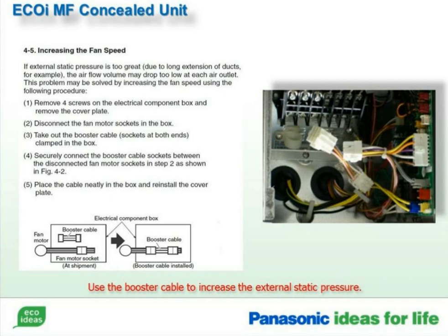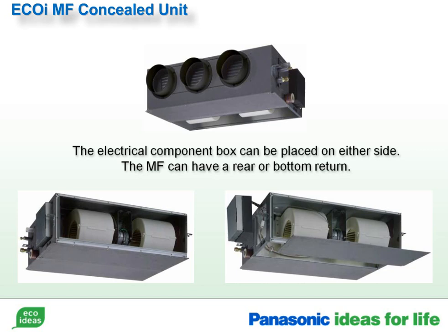To achieve higher airflow with the MF concealed unit, there is a fan booster harness supplied in the electrical compartment. This cable is installed between the fan harness and the circuit board harness. It increases the RPM of the motor. The MF concealed unit comes from the factory set up to use the rear return, but the bottom panel can be moved to the back of the unit to allow for a bottom return. A filter and rack are field supplied. If needed, the electrical compartment can also be moved to the opposite side.